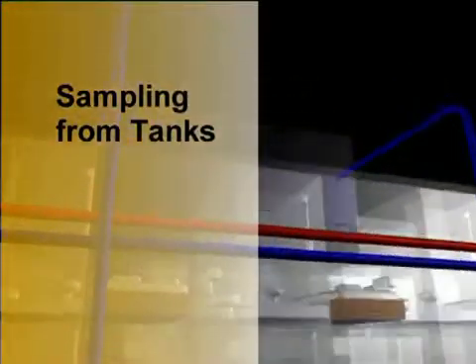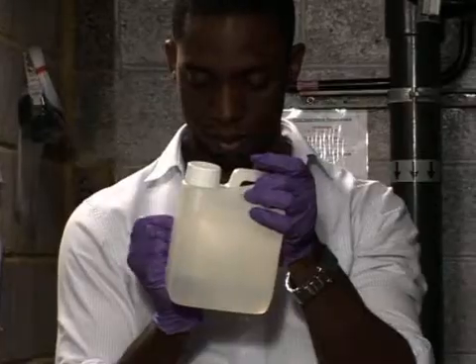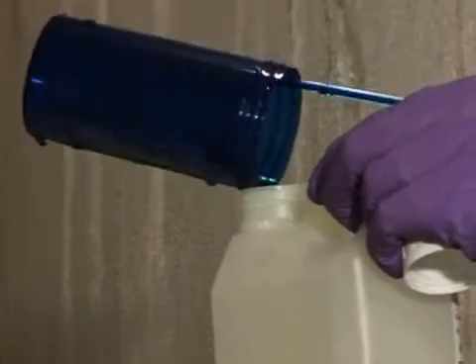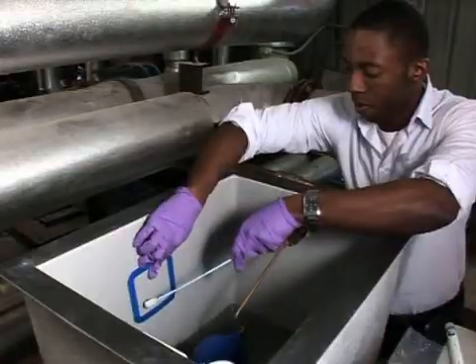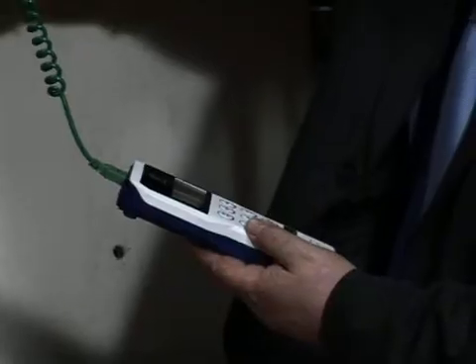If they can be accessed safely, examine inside tanks and collect dip samples or by siphoning water out of the tank. The inside of the tank should not be dirty or excessively corroded. Water should be clear, with no obvious scum or film on the surface, which would indicate insufficient turnover. There should be no more than 24 hours storage in any tank. Water temperature should be very close to the temperature of the incoming mains, and below 20 degrees Celsius.